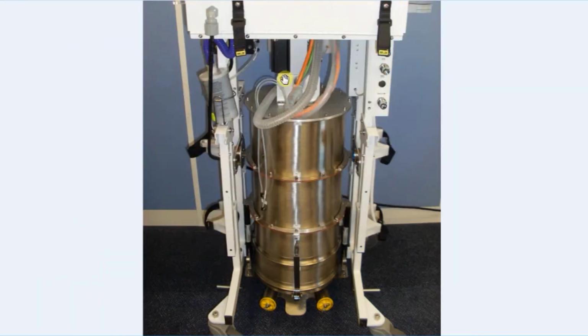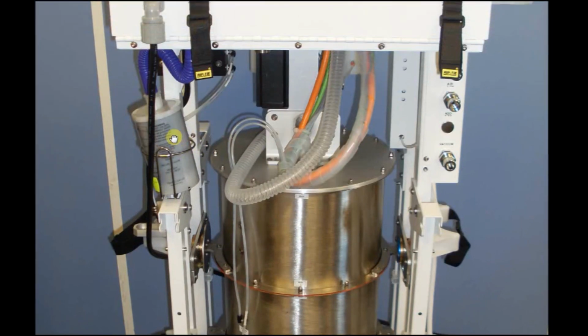One other thing we can see from the back, if we zoom up here, is we have an F-air canister here, or charcoal canister, which comes from the evacuation valve from the machine. Now with scavenging and normal use, this F-air canister is rarely used. It's there really to have 2 catch-all or security functions. If for any reason the scavenging or waste system isn't operating sufficiently to remove waste gas from the system, then the pressure that's generated will force it out through the F-air canister. The activated charcoal in here will remove the agent in use, and only clean air will be let into the room.